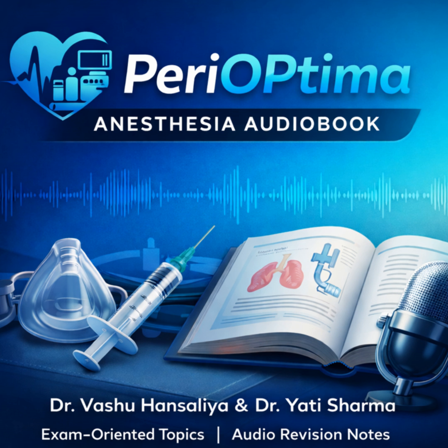Okay. And briefly, the scavenging system. Its main purpose is environmental safety for the staff and the OT. It collects waste anesthetic gases from the APL valve and the ventilator relief valve and vents them safely outside the operating theater. Why is that important? To prevent the OT staff from chronic exposure to waste anesthetics. In early literature, this was linked to health issues like spontaneous abortion and other problems. It can be an active system with a fan or suction, or a passive one.